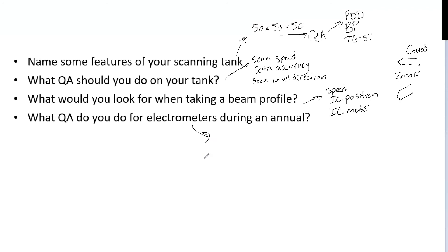Finally, what QA do you do on electrometers during an annual QA? First, it has to be calibrated. Very first thing that you should check. Second, you want to cross-examine this electrometer with a second electrometer. And then you could also check this with a multimeter. So those are the things you would want to test your electrometer before using it.